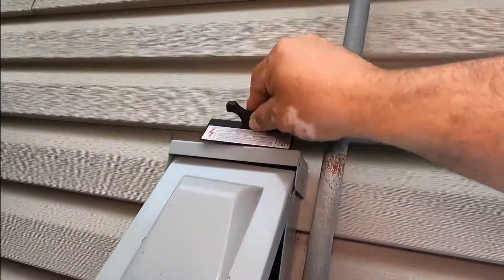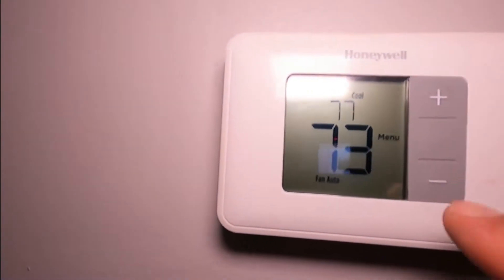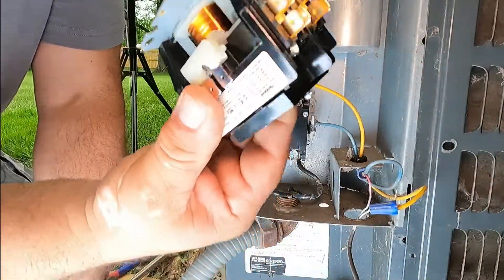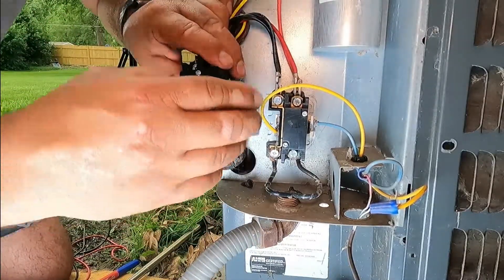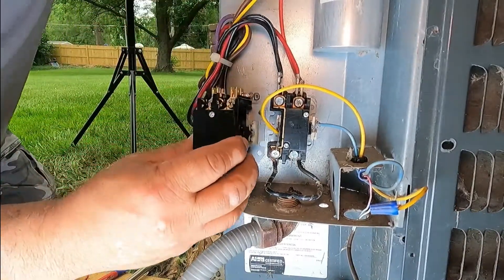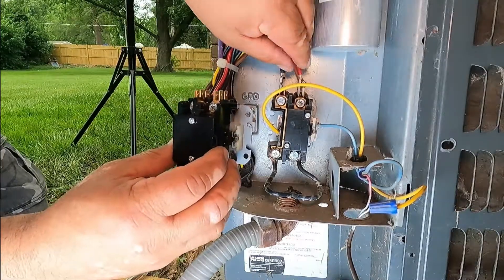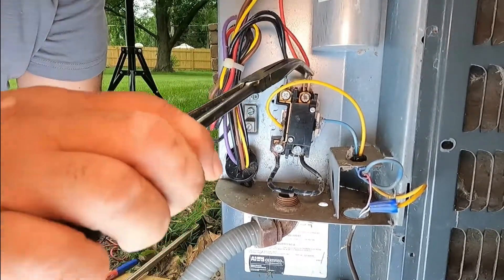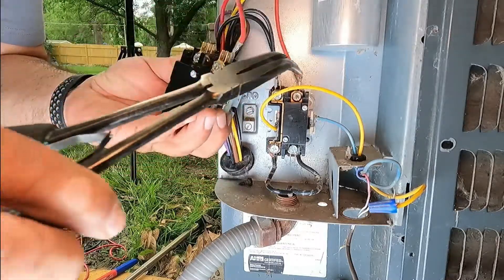To replace it, let's make sure there's no power. We're going to pull our switch disconnect and put it on top of the unit so you know it's not on. We also have to make sure that the thermostat is not calling for cooling. You're going to place your contactor in the upright position and then disconnect the wires. Let's start with the right side — whatever wires you remove from this side, you're going to put them on this side of the new one.